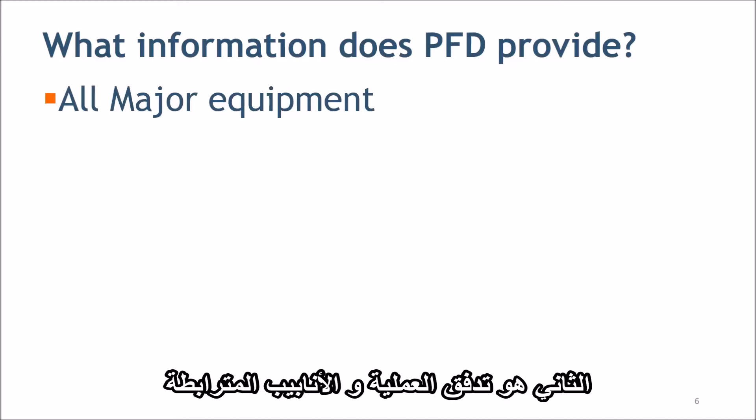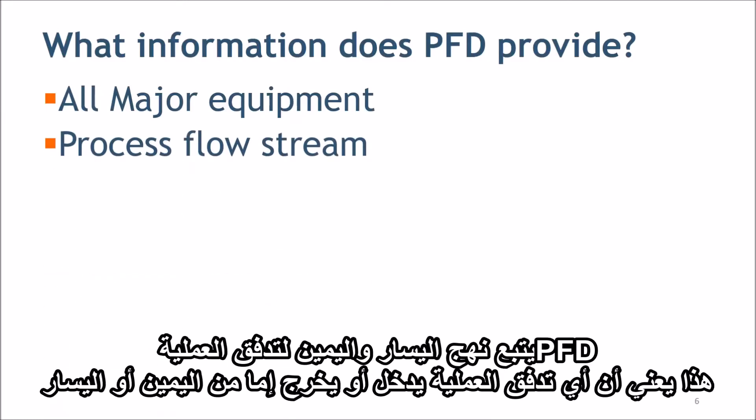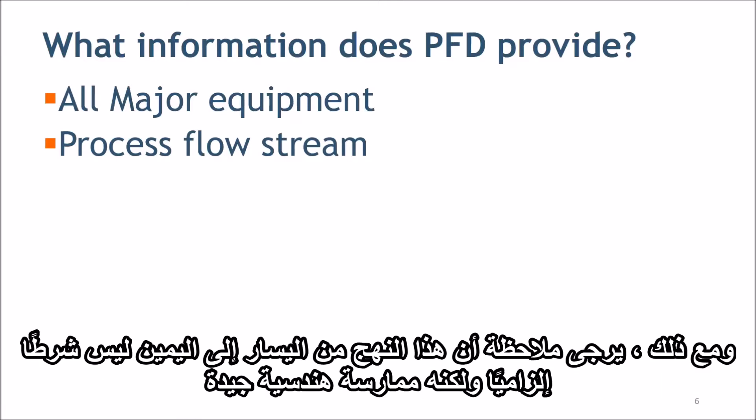Second is process flow stream or interconnected piping. PFD follows a left-right approach for the process flow. That means any process stream enters or exits either from the right or left. However, please note that this left-right approach is not a mandatory requirement but a good engineering practice.